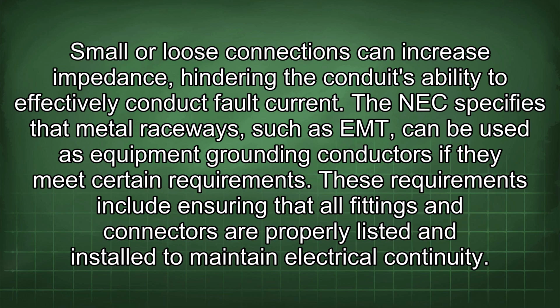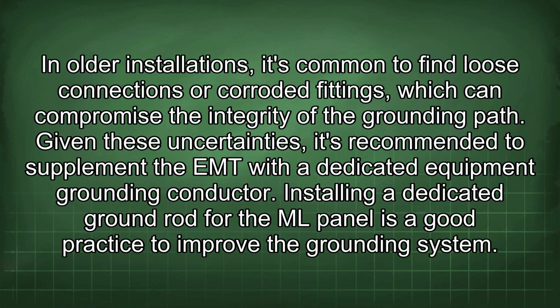The NEC specifies that metal raceways, such as EMT, can be used as equipment grounding conductors if they meet certain requirements. These requirements include ensuring that all fittings and connectors are properly listed and installed to maintain electrical continuity. In older installations, it's common to find loose connections or corroded fittings which can compromise the integrity of the grounding path. Given these uncertainties, it's recommended to supplement the EMT with a dedicated equipment grounding conductor.